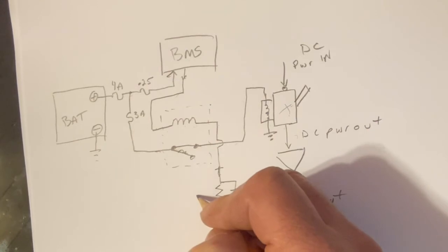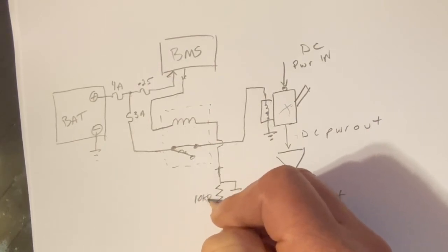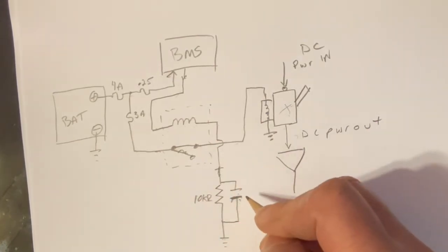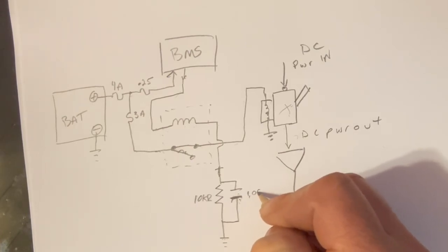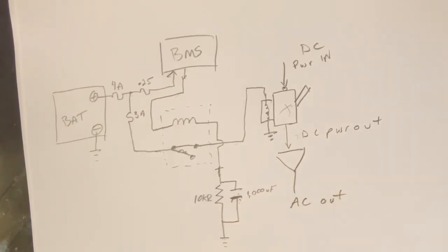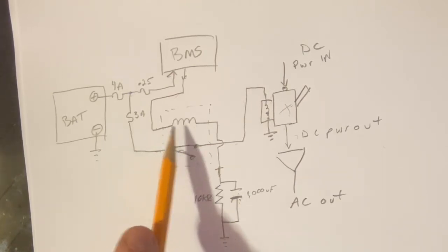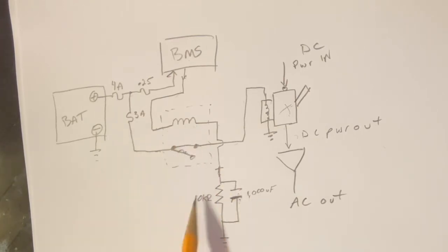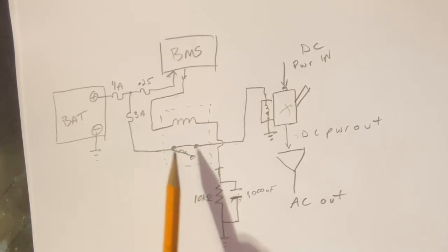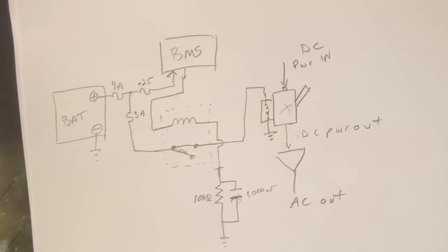So in this case, we have a 10 kilo ohm resistor and a 1000 microfarad capacitor. The math works out that this is about a 10-second delay. In reality, it's only about 2 seconds because of the nature of how the coil works and the charge and discharge characteristics of how this circuit bleeds itself off and when this coil is actually activated. So you may need to do some trial and error based on the equipment that you end up with.